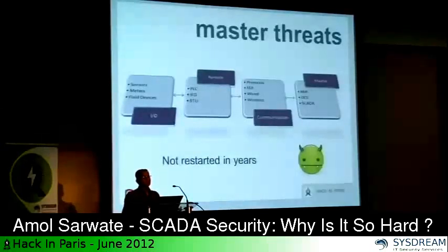There are some systems which are not restarted for years, and when we ask why your systems are not restarted, the simple answer is that they are not confident that after the restart or the reboot the system will even come up. We found that a little bit funny, but that is the stage at which a lot of SCADA systems are running: old off-the-shelf software, Windows NT or Solaris, really older versions, that are not patched.